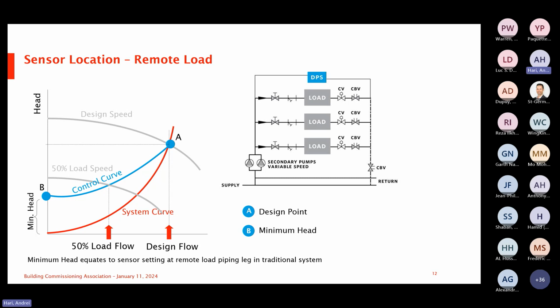The other challenge now, though, is that once the DP sensor is located in the system, it's fixed. And if it's in the wrong location, you have to basically drill, tap, find a new location, and then run your conduit and your wiring at that new location. So it becomes very much of a hard-piped or a fixed application in the system that doesn't lend itself to adjustment if there are issues like zero flow or starving points of the system.